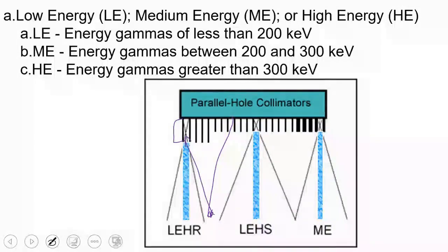Can you imagine? The longer the collimator, the more it will block the scattered photon coming at an angle, unlike when it is short, where it might allow a photon to pass through. Therefore, my resolution depends on two things: the diameter of the holes being small and the length of the setup being large. These will improve my resolution and reduce my sensitivity, unlike here.